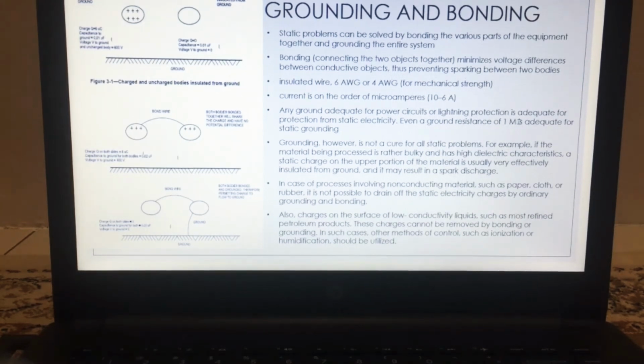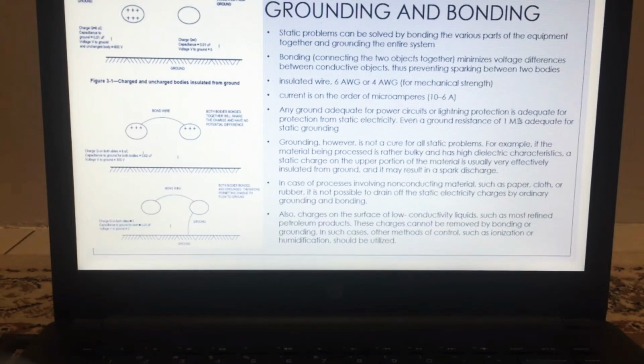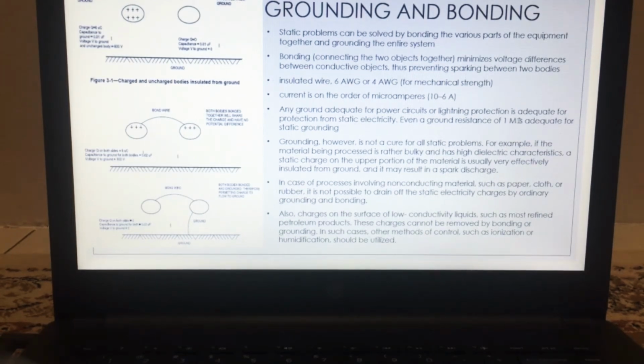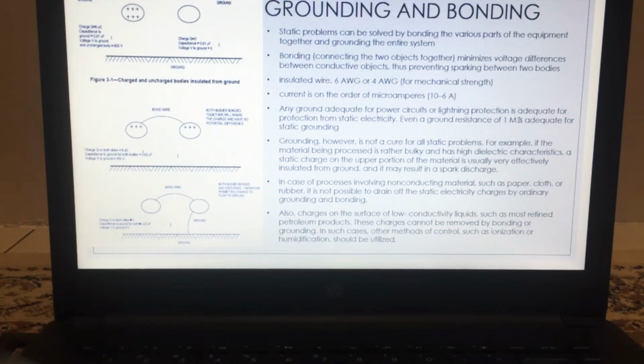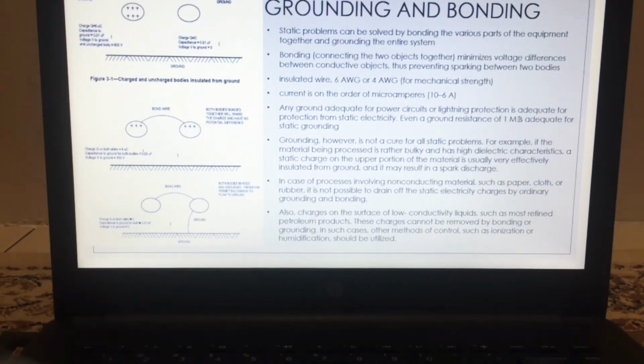In the case of processes involving non-conducting materials such as paper, cloth or rubber, it is not possible to drain off the static electricity charge by ordinary grounding and bonding. Also, charges on the surface of low conductivity liquids such as most refined petroleum products cannot be removed by bonding or grounding. In such cases, other methods of control such as ionization or humidification should be utilized.